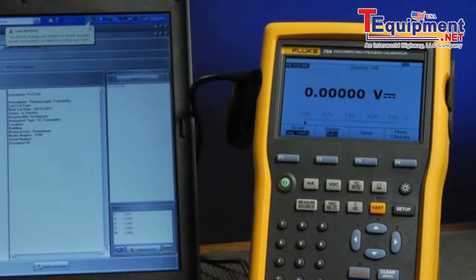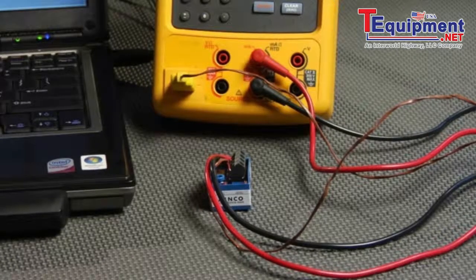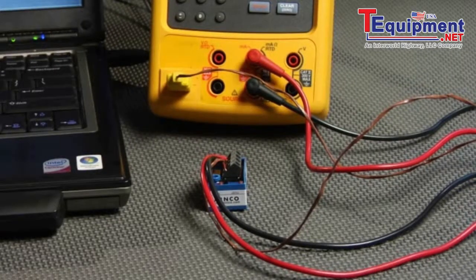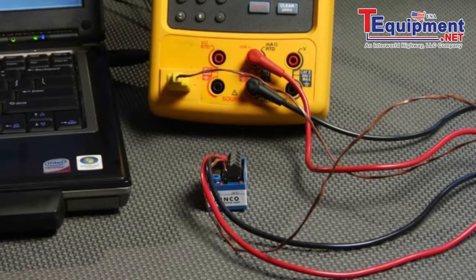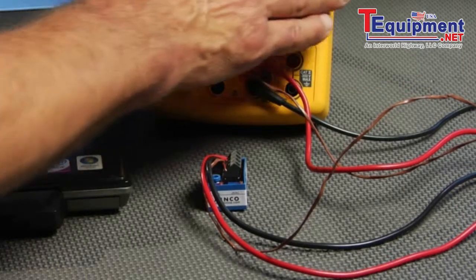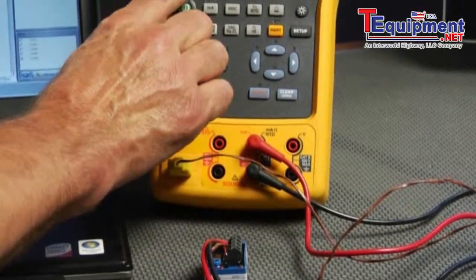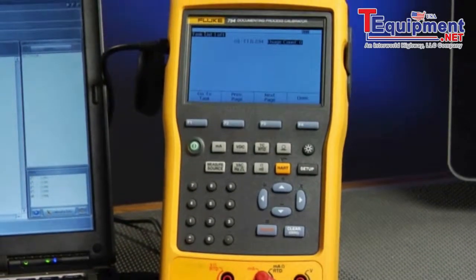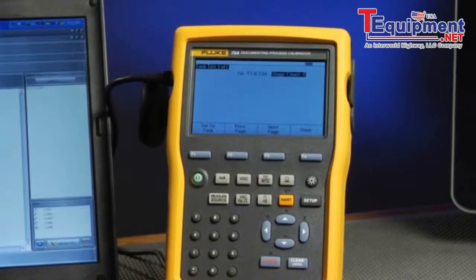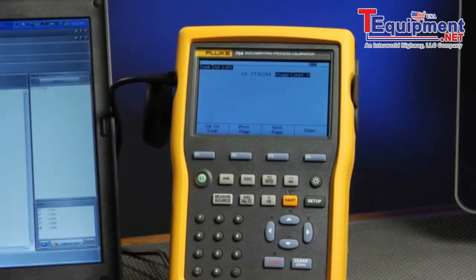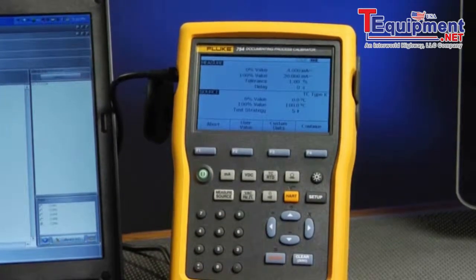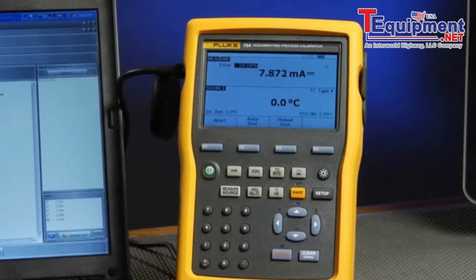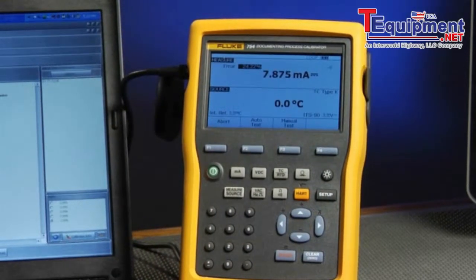Now we would perform the calibration of the tag that we've downloaded into the calibrator. Next we're going to select the task loaded into the calibrator. The task is configured for a Type K thermocouple transmitter. Select more choices and task. Here you see the task that was loaded into the calibrator from the DPC track 2 software. Press enter to select the task and then continue to configure the calibrator for the test.